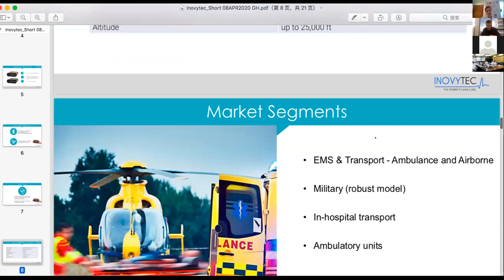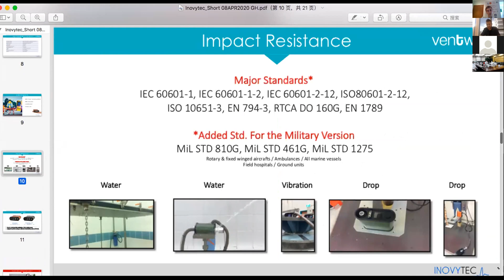Yes, go another one, scroll down. Yes, so the ventilator was manufactured to withstand the harshest standards for water and dust resistance, vibration, drop, all of the environmental standardization for a medical ventilator. We have tested the Ventway Sparrow not only for that, but also for electromagnetic compliance and all of the needed standardization to work both in and out of the hospital. Just before I go through, I would say that the ventilator is authorized by the CE for the European Union and also by the FDA. We have also got the TGA approval for Australia, and we are currently working on the CFDA certification, which is not completed yet.